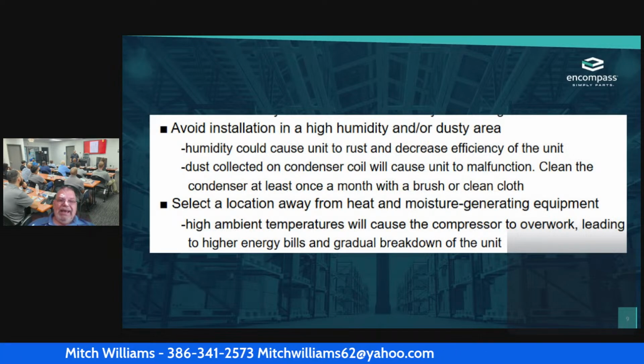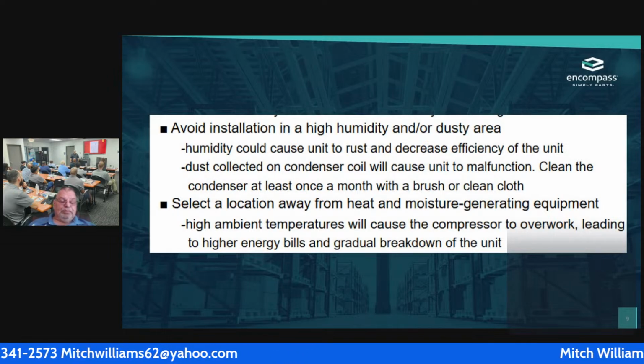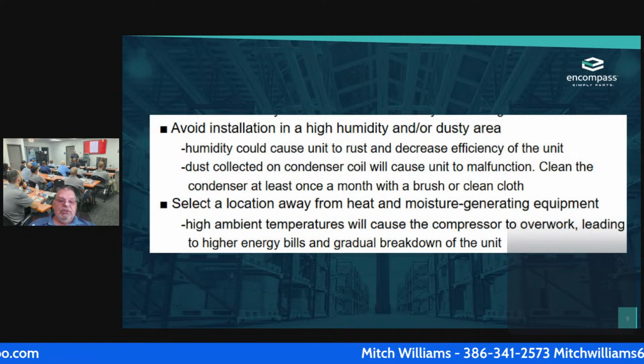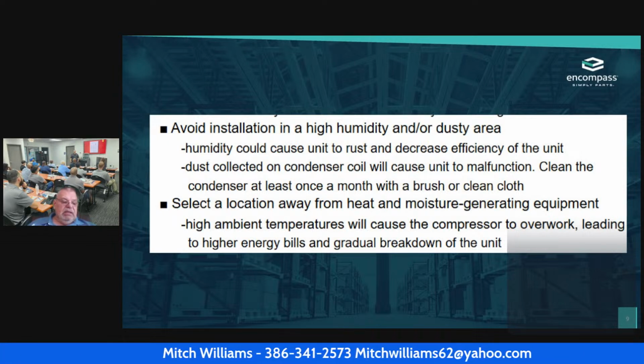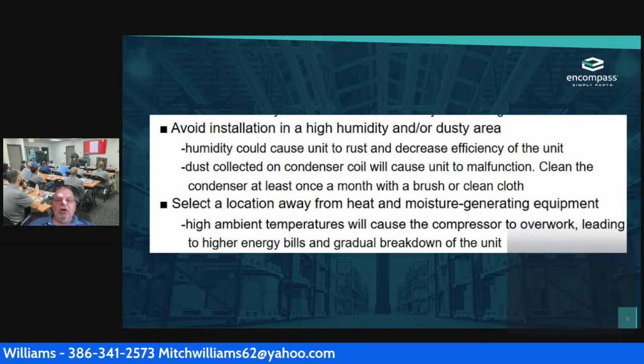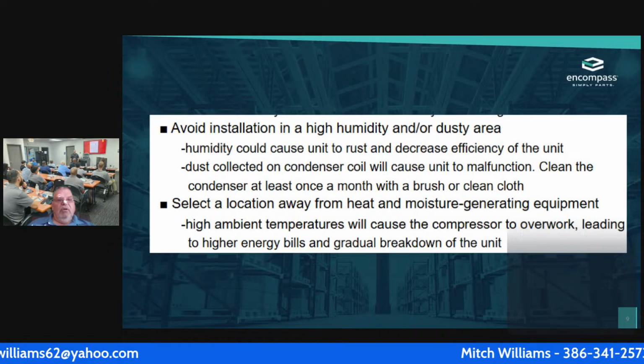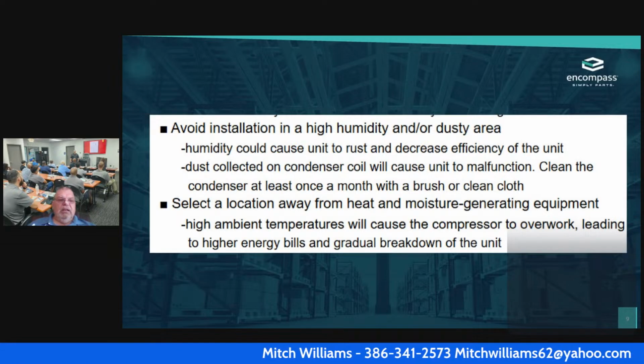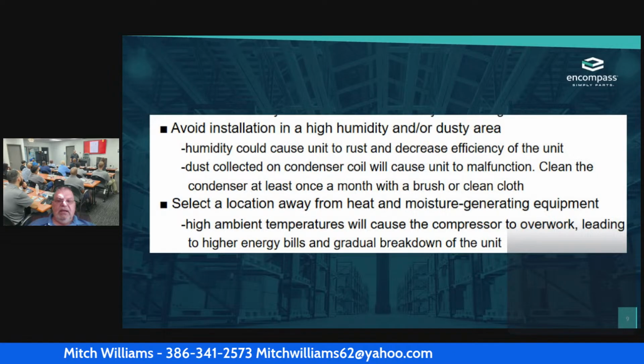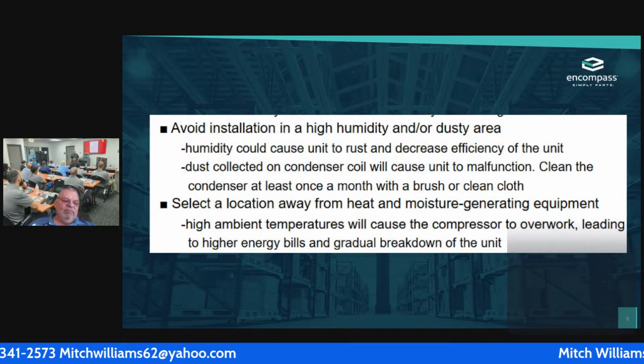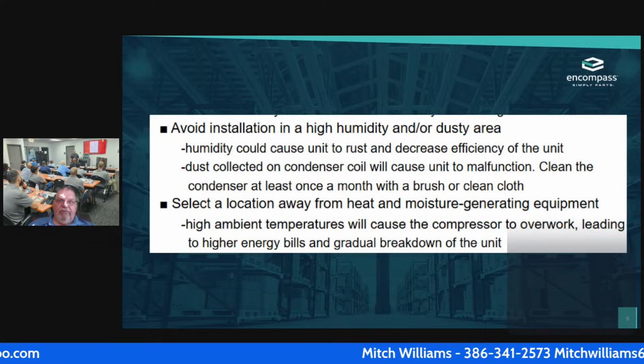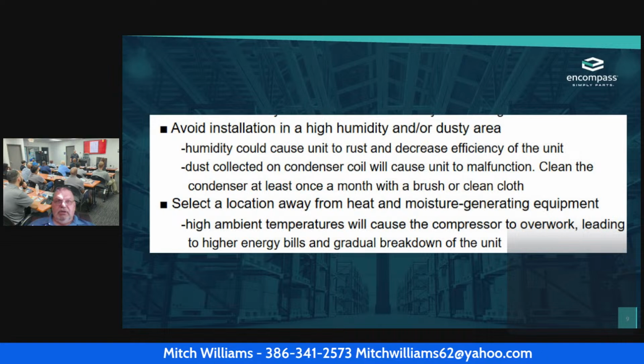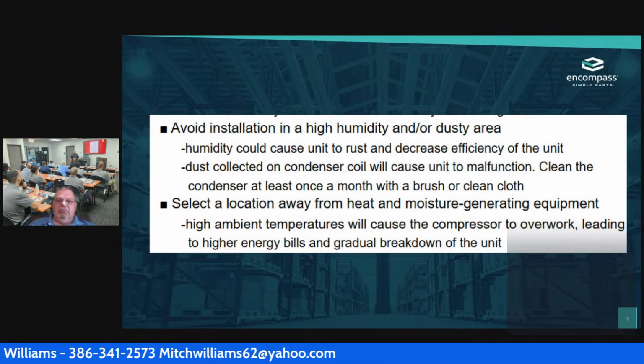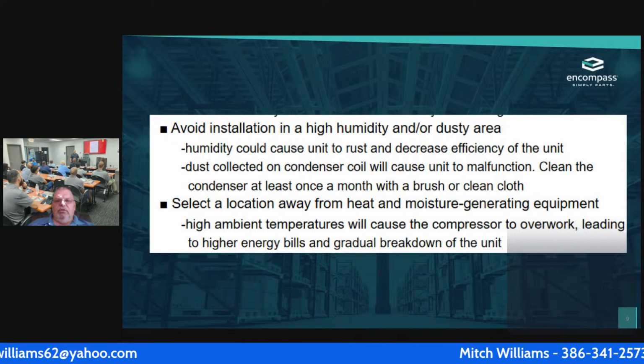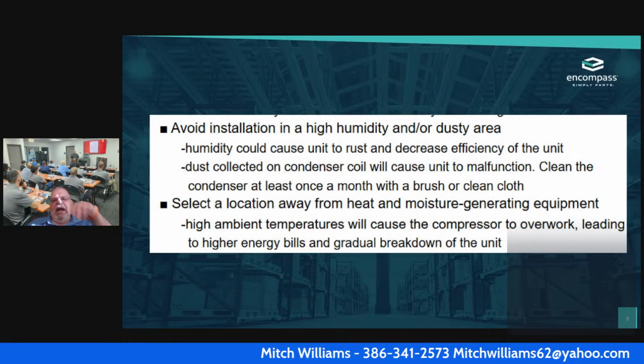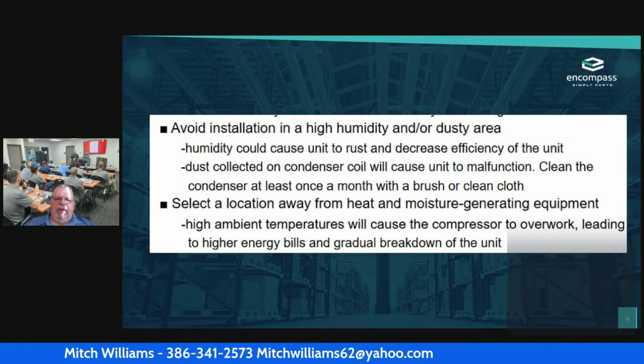So these are the guidelines that are given to whoever the recipient of this unit is. It tells them that they need to clean this at least once a month. They need to brush it, or they need to use a clean cloth. Well, here's the problem. If I'm brushing it left to right instead of up and down, I'm bending the fins. So now I have to have my fin brush. So you've got to be very careful. You're hoping that the customer really doesn't adhere to this, because they'll just get in there and mess it up. And then you always make sure, with my tool pouch, I have a fin brush that I keep in my tool pouch.